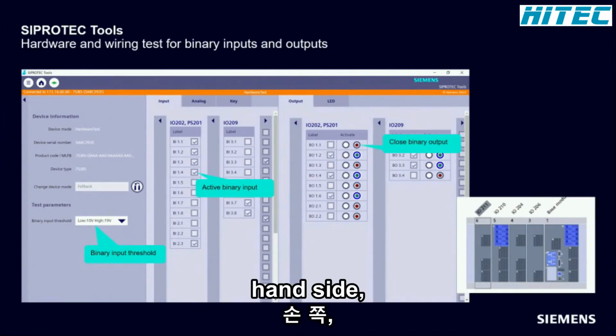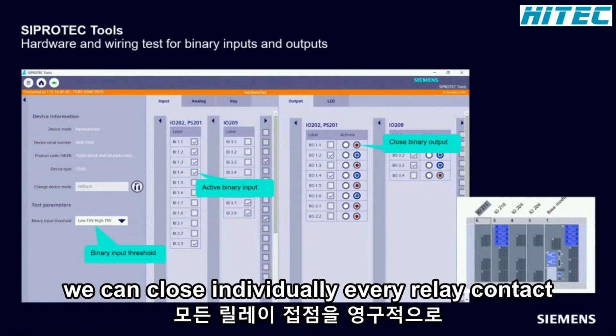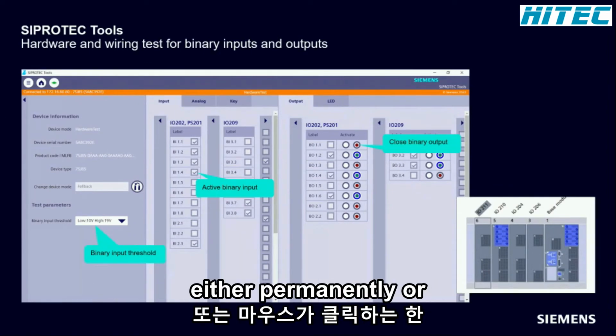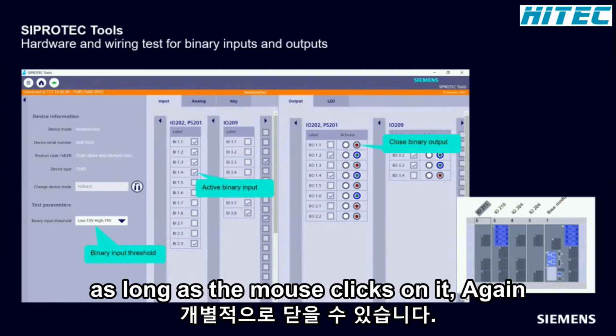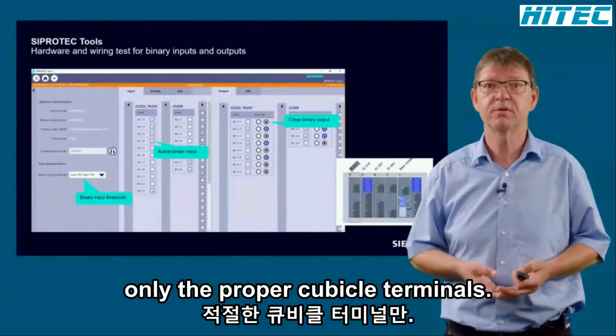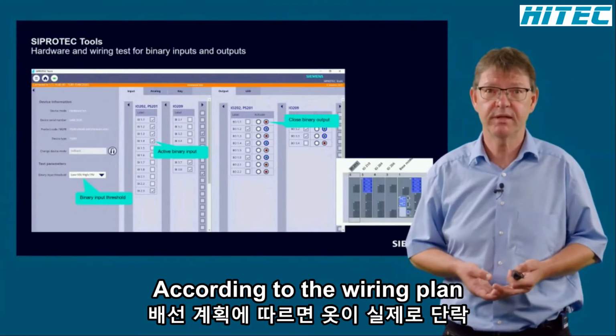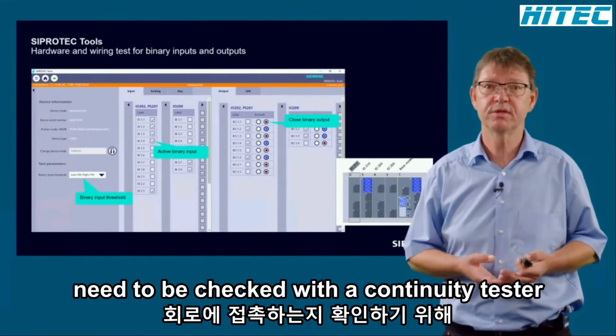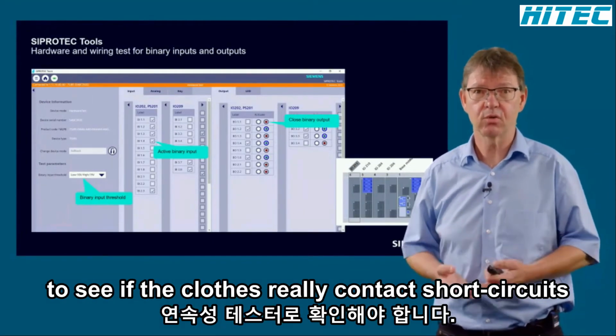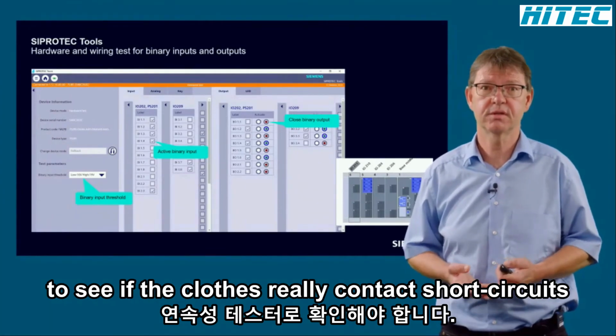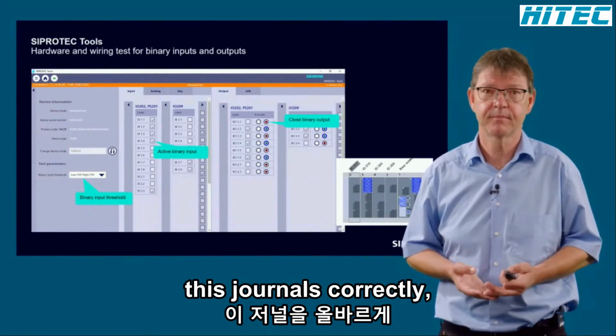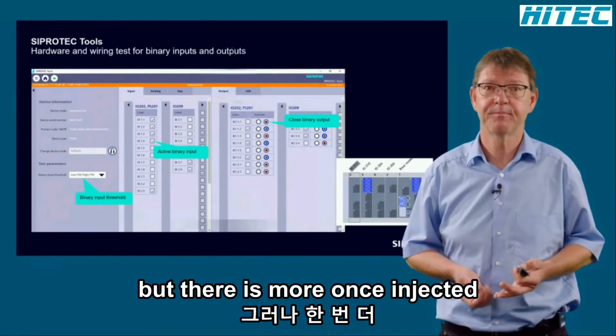On the right-hand side, we can close individually every relay contact, either permanently or as long as the mouse clicks on it. Again, only the proper cubicle terminals, according to the wiring plan, need to be checked with a continuity tester to see if the closed relay contact short circuits these terminals correctly. But there is more.